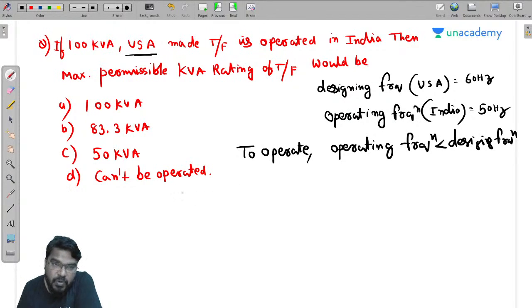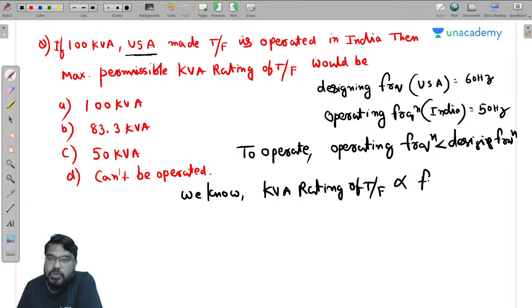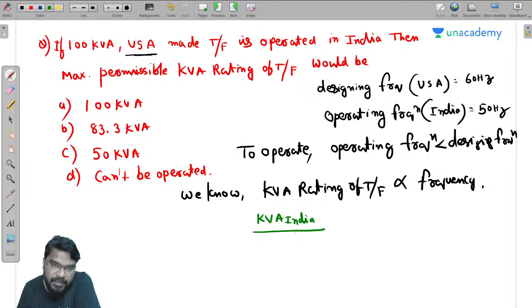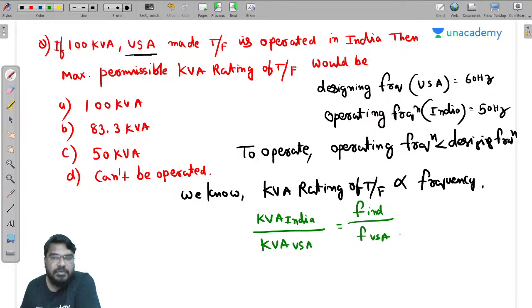So we know that the kVA rating of the transformer is directly proportional to the frequency of the transformer. Got it? So you can write the kVA rating of the transformer in India divided by the kVA rating of the transformer in USA is equal to frequency in India divided by frequency in USA, right? So now substitute: the kVA rating in India is equal to 100 multiplied by 50 divided by 60 kVA.